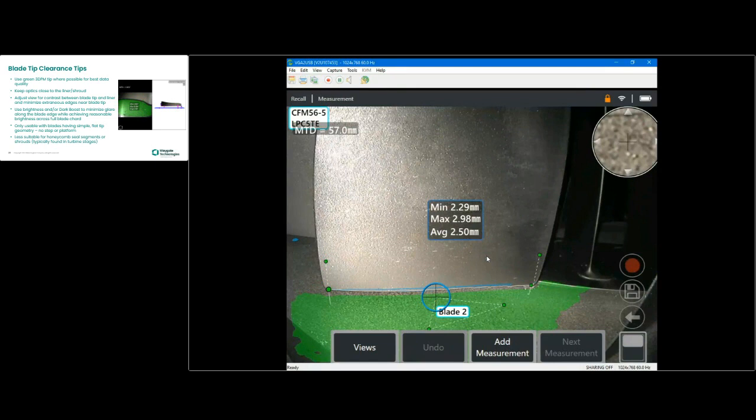So all of those cursors are automatically applied by the device. And these two dotted lines represent the extremity upon which the tip of the blade tip data is taken from. The depth data are taken from that. So the fourth point from the depth isn't shown on this slide. It's highlighting the front and the back of the blade that has been detected by the instrument. If I was to move the front and the back, the corresponding maximum and minimum value, it will adjust.